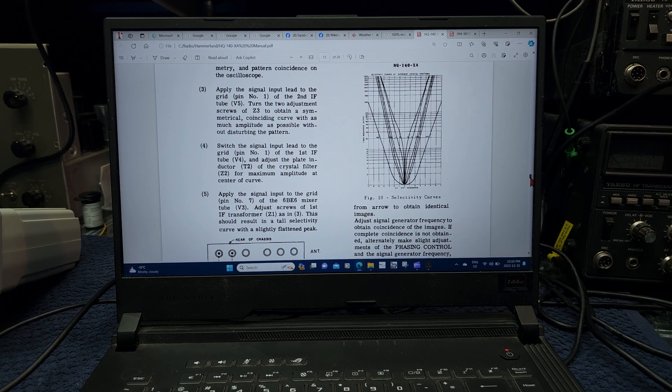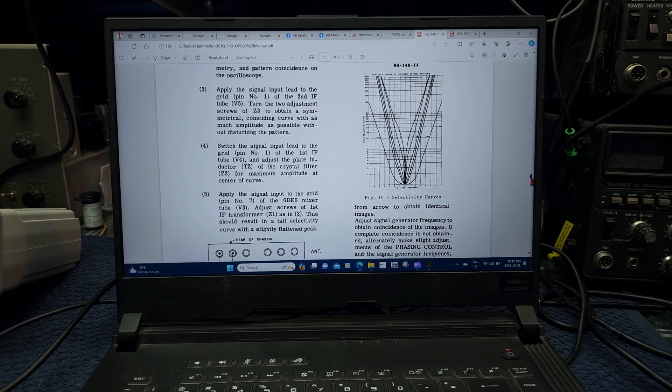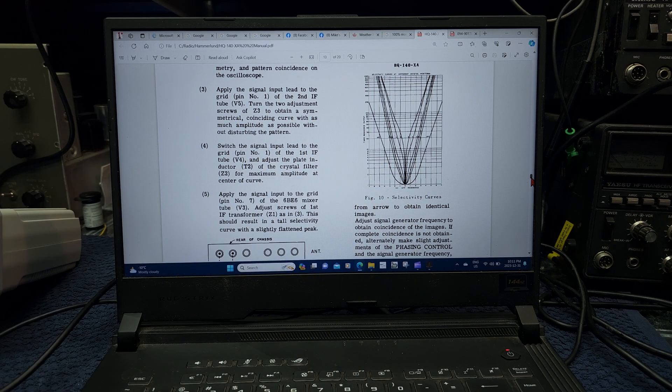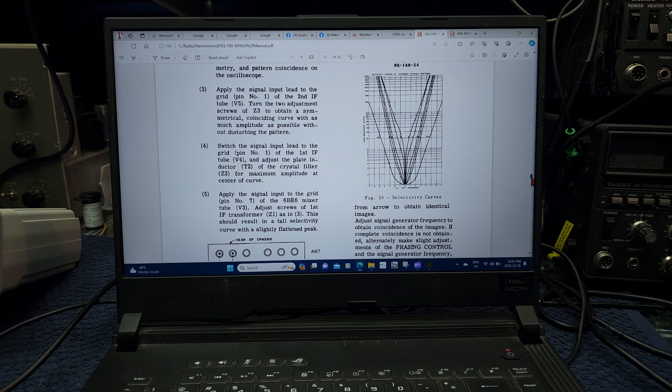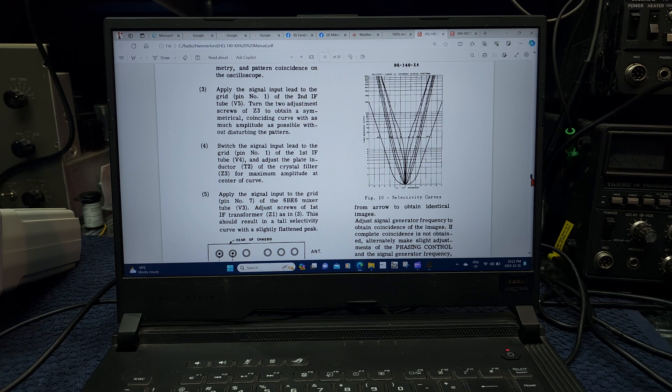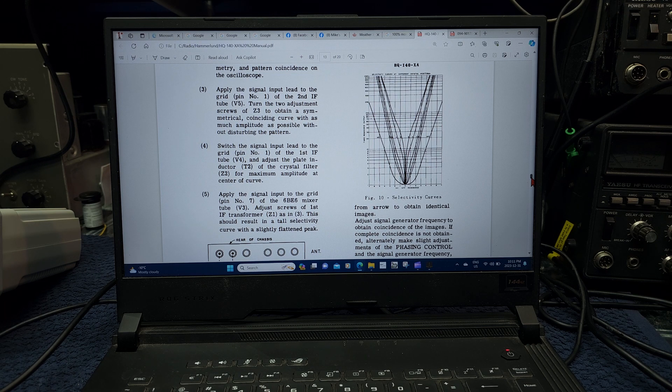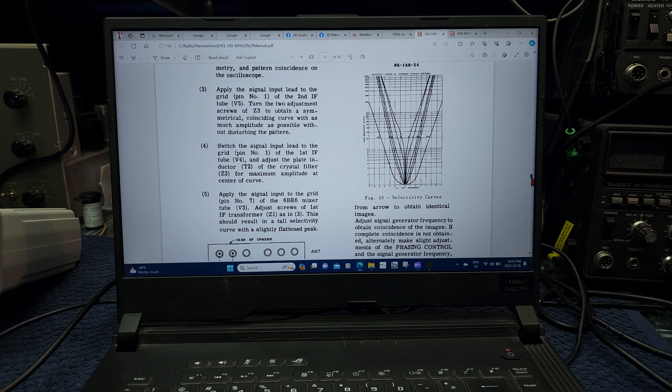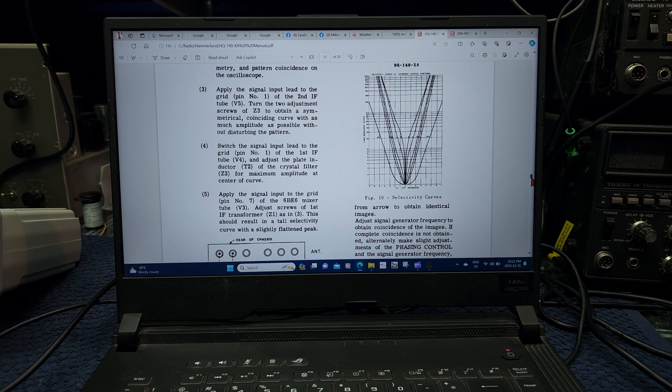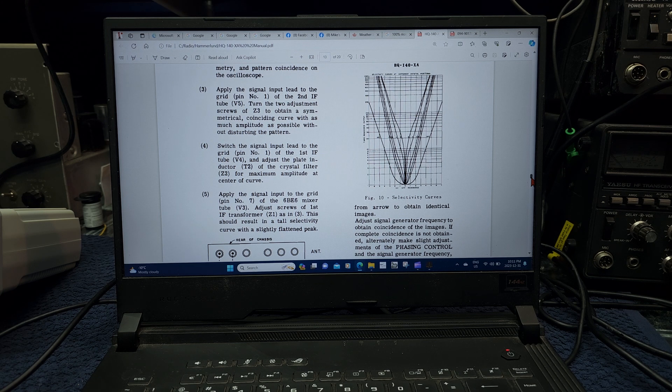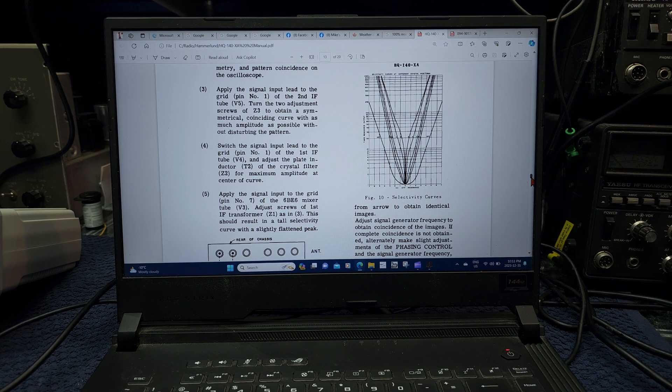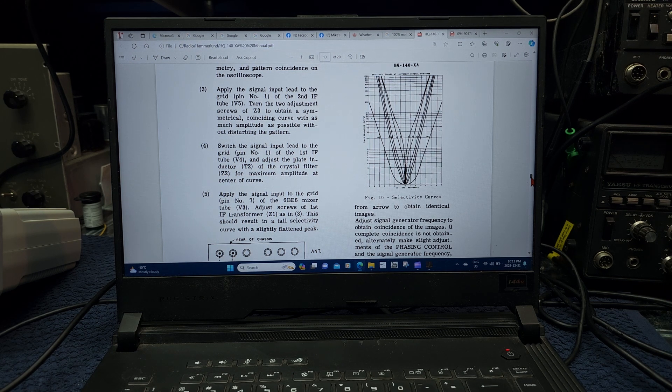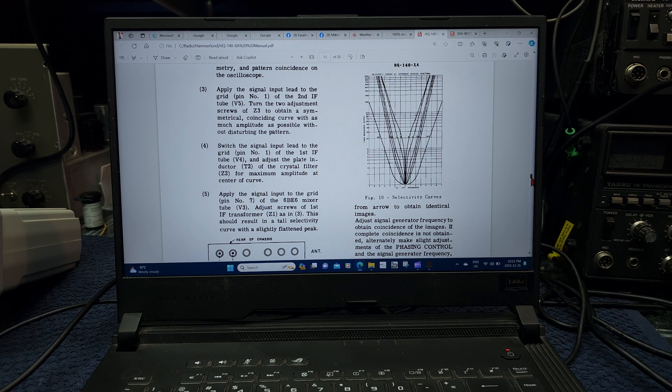This is the manual of the Hammarlund HQ-140XA, and as you can see here, they have a crystal filtering system here that has five distinct settings. And there's a very long procedure to go through here. And having a sweep generator and a spectrum analyzer to go through and make sure that all of these five settings are falling within the manufacturer specification, it's very handy. There's really not another way to do it.